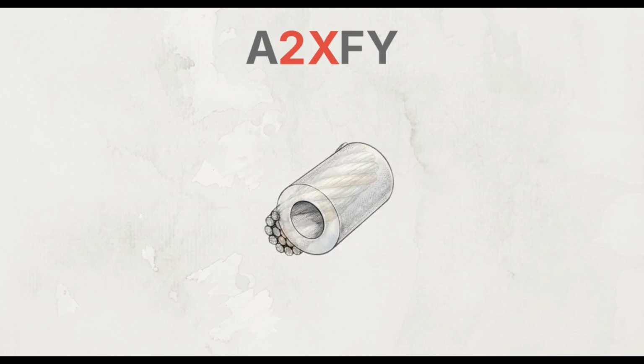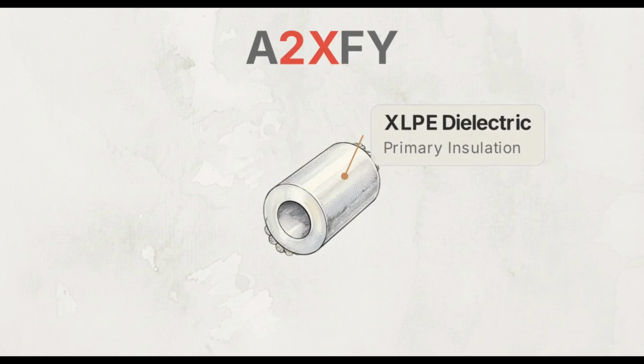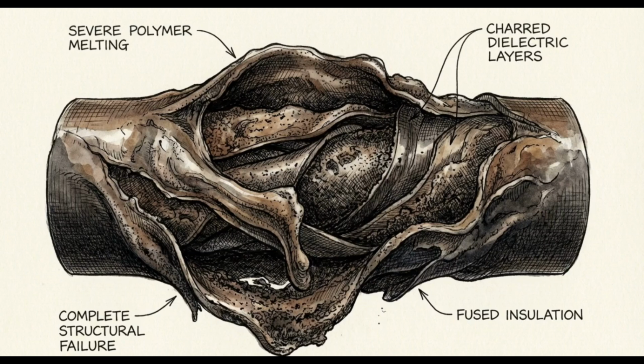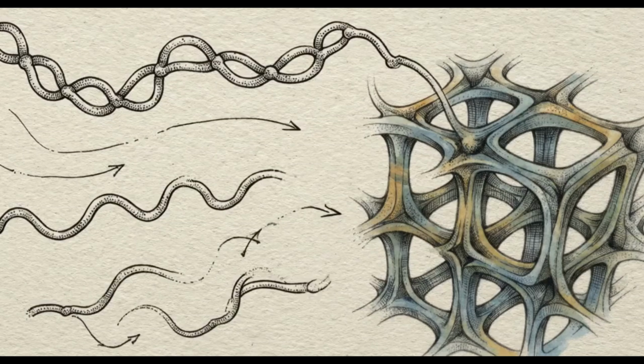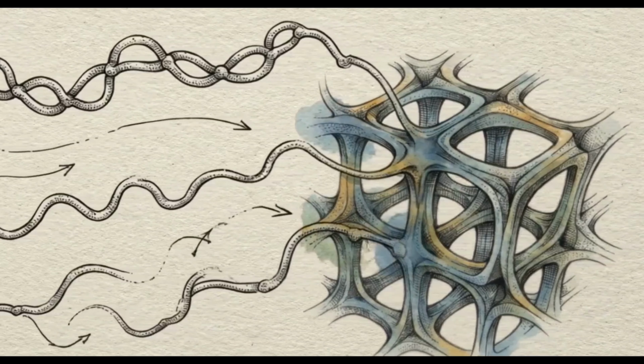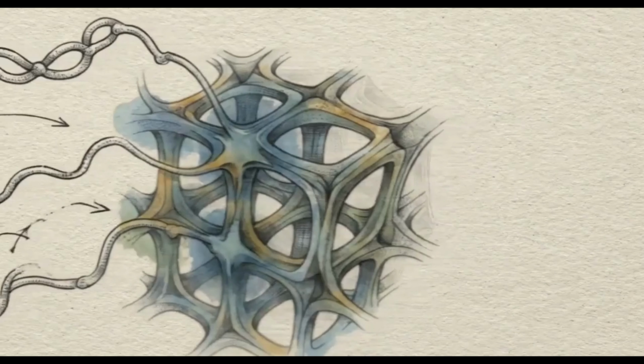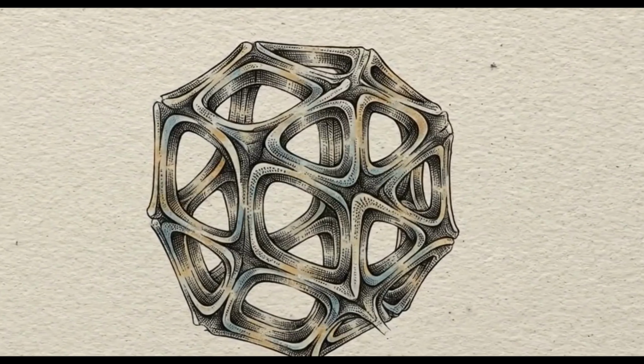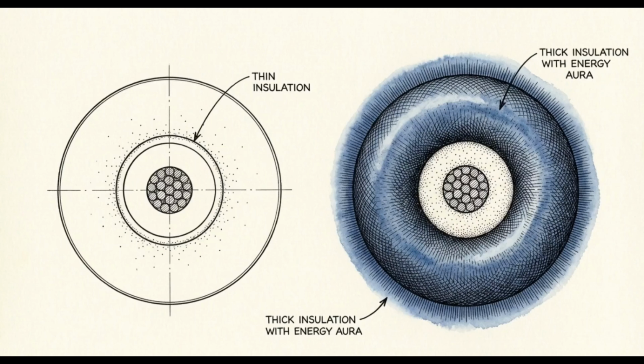The 2X designates the primary dielectric insulation, cross-linked polyethylene, or XLPE. Legacy thermoplastics like PVC are limited by a continuous operating temperature of 70 degrees Celsius, which restricts their use in modern high-load infrastructure. Through vulcanization, polymer chains in XLPE link into a rigid three-dimensional lattice. This allows the insulation to withstand extreme short-circuit temperature spikes without melting. The thickness of this dielectric layer is determined by system grounding. Ungrounded systems require thicker insulation to handle prolonged phase-to-phase voltage stress during faults.